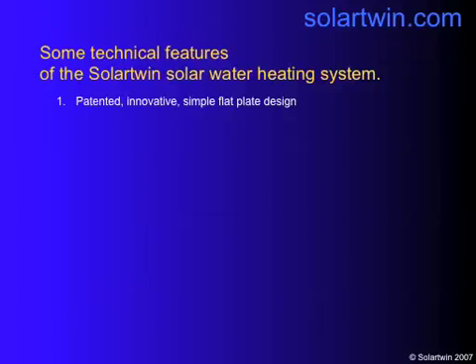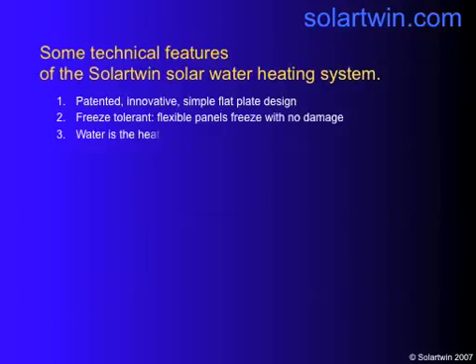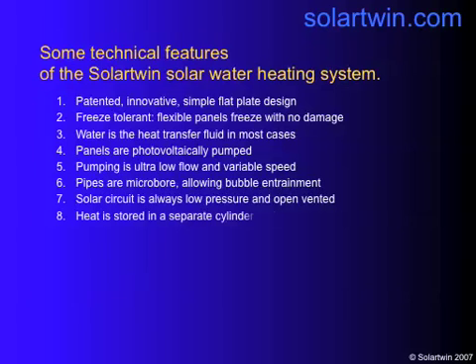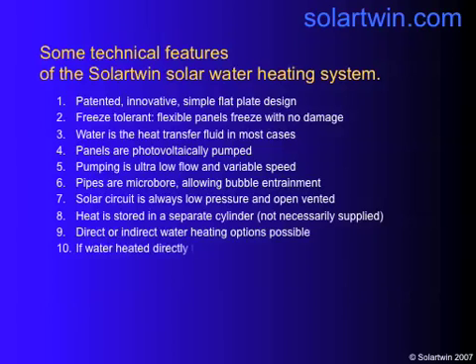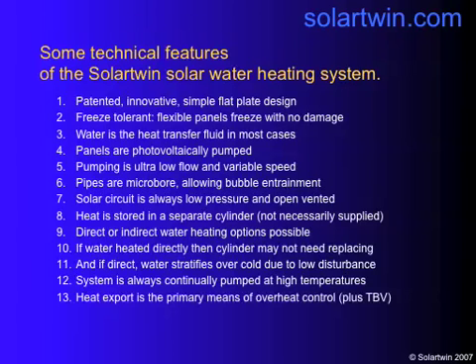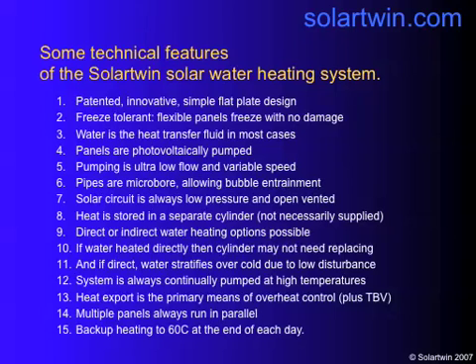Looking at the technical features of Solartwin: it's a patented simple system that can freeze without cracking. Water is the heat transfer fluid. The panels are pumped by solar electricity at very low flow and variable speed. The pipes are microbore so bubbles can get out without valves on the roof. It's a low-pressure open-vented system. Heat is stored separately and can be heated directly or indirectly, but usually directly — meaning you don't need to replace the cylinder. Water will stratify over the cold and you'll get continual pumping at high temperatures, which means you can export heat. Multiple panels can be run in parallel, and you must back up your heating to 60°C at the end of the day.